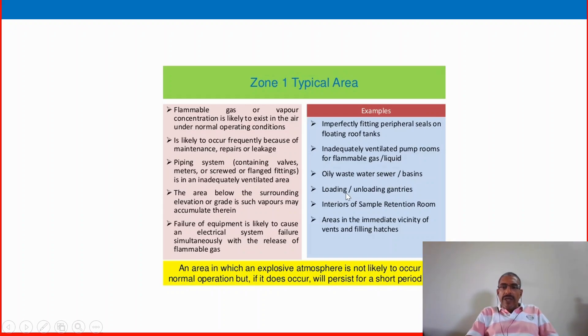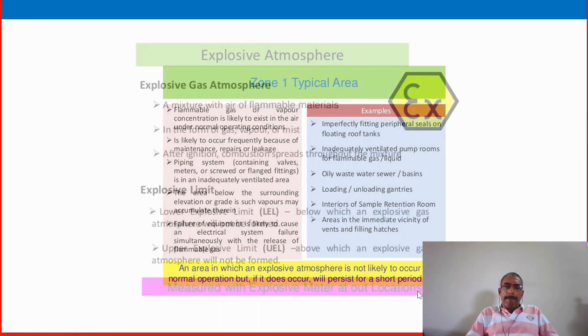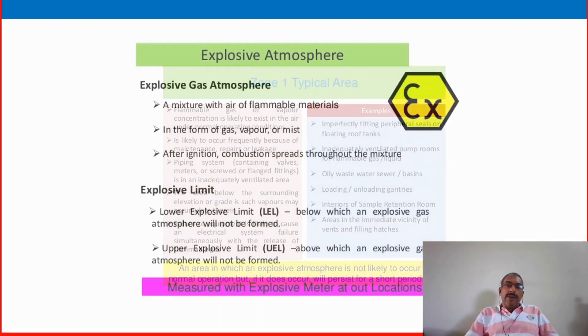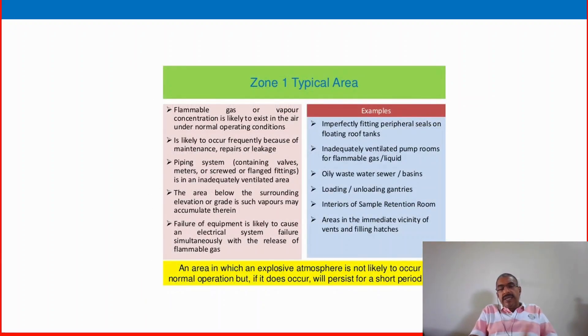Zone 1 examples include: oily wastewater sewers or basins, loading and unloading gantries, interiors of sample retention rooms, and areas in the immediate vicinity of vents and filling hatches. Zone 2: an area in which an explosive atmosphere is not likely to occur in normal operation, but if it does occur, will persist for a short period only. Zone 2 is already discussed — it is more than 3 to 4 meters away from Zone 0.